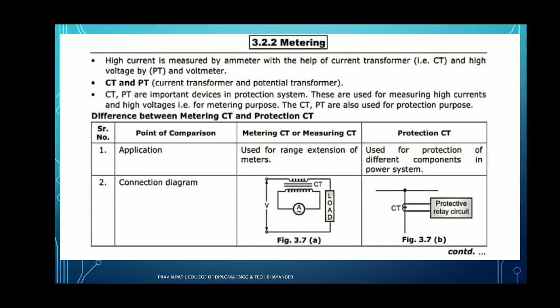Next, we have to see the metering. A high current is measured by an ammeter with the help of a current transformer, known as the CT, and high voltage is measured with the help of the potential transformer or voltmeters. CT and PT, that is the current transformer and potential transformer, are important devices in protection systems. In switchgear systems also, these are used for measuring the high current and high voltage, that is for metering purposes. The CT and PT are also used for protection purposes.